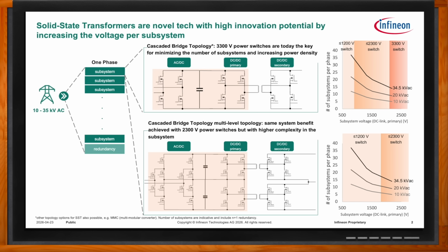If we now do the math, and take the example of 34.5 kV, you can read out based on the graph in the upper right corner that a design for 34.5 kV based on 1200 volts would need more than 35 subsystems, while if you would decide to go for 3300 volt, you would only need less than 15. So there is a tremendous complexity reduction with higher voltage.